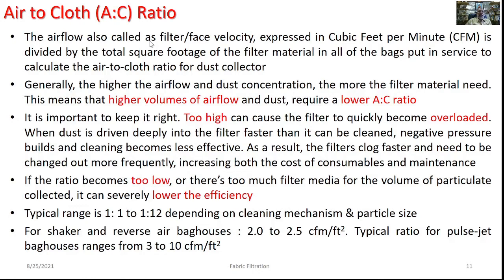It is necessary to maintain the air-to-cloth ratio at the right level. If the ratio is too high, it can cause the filter to quickly become overloaded. On the contrary, if the ratio is too low or there is too much filter area, it would hamper the efficiency of the baghouse considerably. Typically, the A:C ratio could be 1:1 to 1:12 depending on the cleaning mechanism and particle size to be removed. For shaker and reverse air baghouses, the A:C ratio is in the range of 2 to 2.5 cfm per square foot, whereas for pulse jet baghouses it could be 3 to 10.